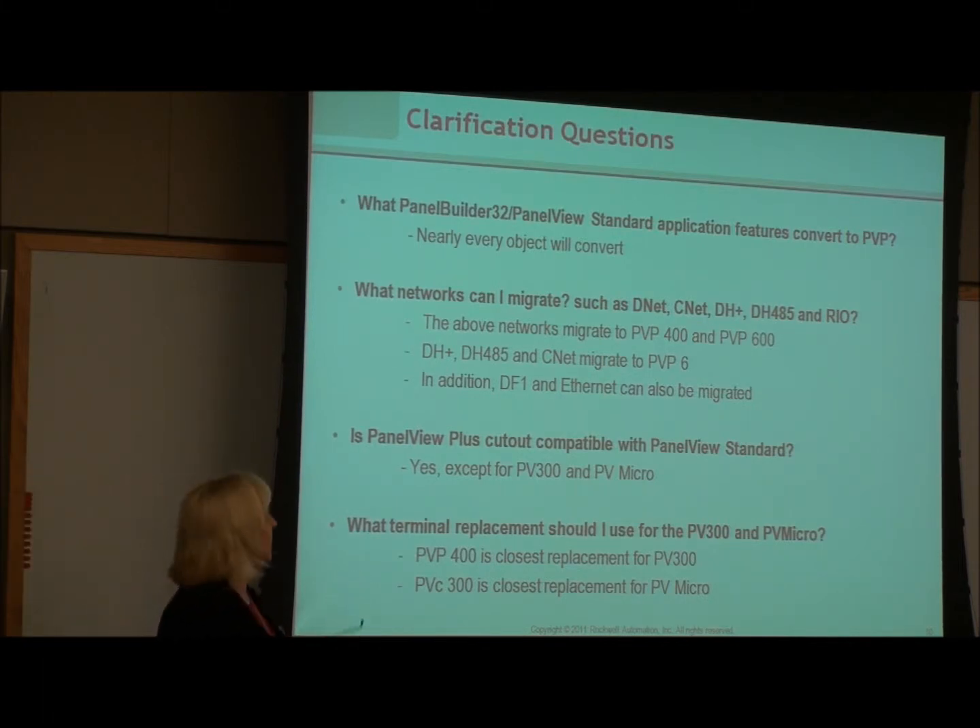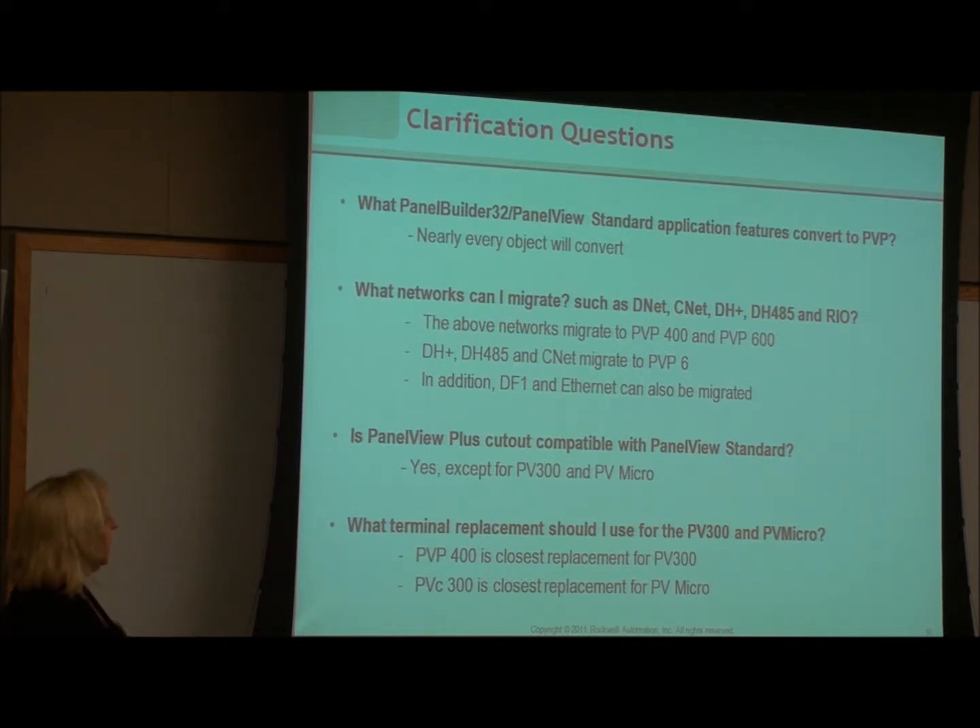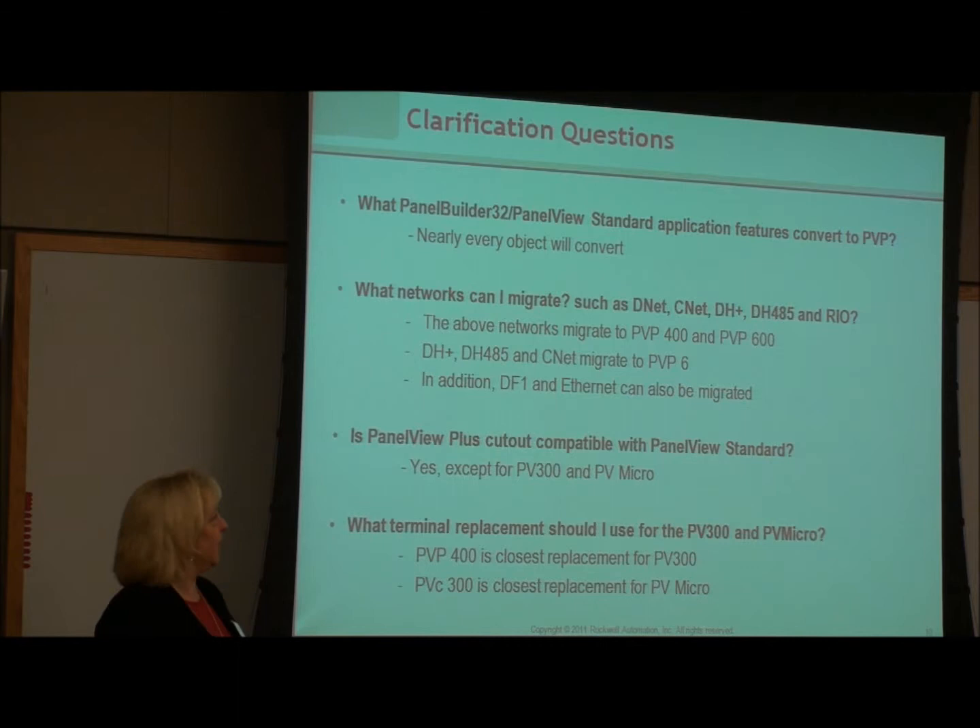Regarding the DH question: DH Plus, DH485, and ControlNet can go to the new PanelView 6 version. Ethernet and DF1 are also convertible. What is not listed there is Remote IO and DeviceNet, which are a sticky situation. If you have Remote IO, that is the most difficult migration — there's the most work involved. DeviceNet is a little bit of work, but Remote IO is by far the most involved.